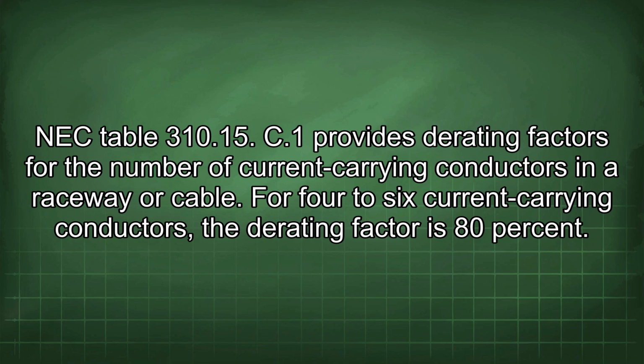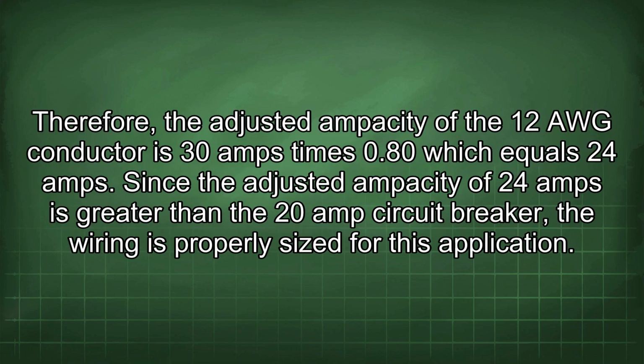C1 provides derating factors for the number of current carrying conductors in a raceway or cable. For 4 to 6 current carrying conductors, the derating factor is 80%. Therefore, the adjusted ampacity of the 12 AWG conductor is 30 amps times 0.80, which equals 24 amps.